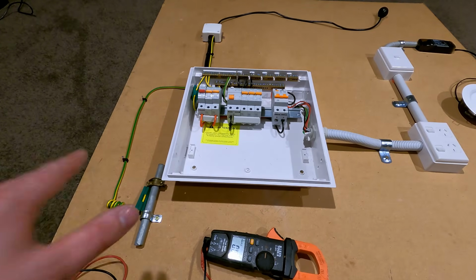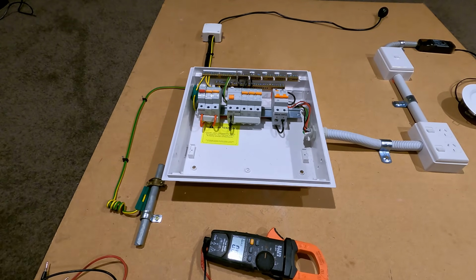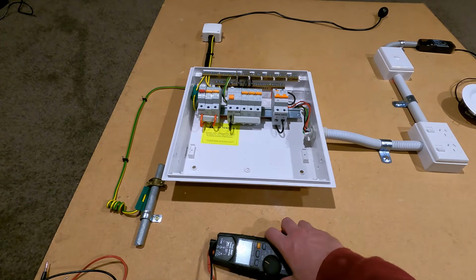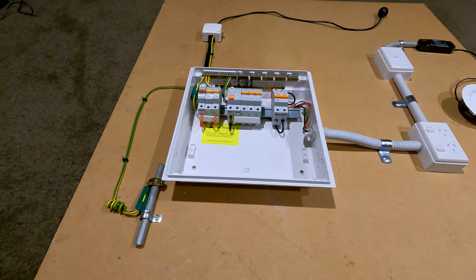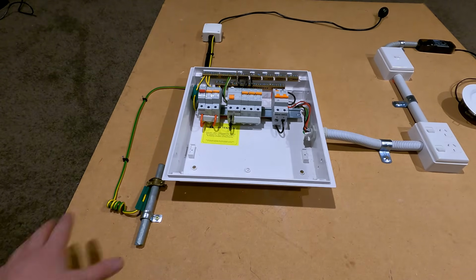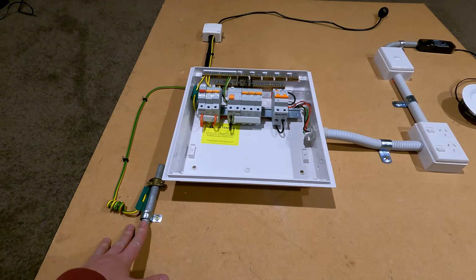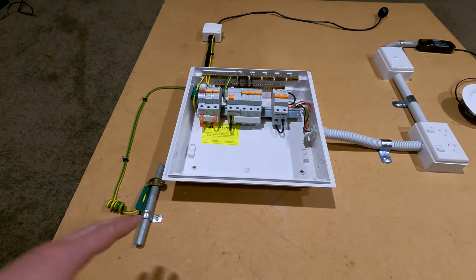So the maximum resistance on any earthing conductor or equipotential bond is 0.5 ohms. So a result less than that is perfectly acceptable. A result more than that and you'll want to fix something. If you had an open loop between the main earthing conductor and the earth bar, check the terminations, check that the clamp's on properly, and check that a builder hasn't cut the cable on you.